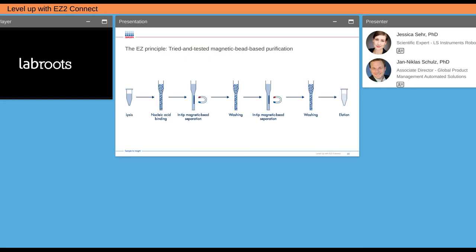So what the instrument is doing is that it works with tips inside, so it really can aspirate liquid, and with the liquid also the magnetic beads, and then a magnet can be put in close proximity to this tip to attract the beads, and the liquid can be exchanged and also transferred then to the next well, and so on and so on. And this is very unusual for an instrument in this size. Normally benchtop instruments work with static magnets and only transferring the liquid, but keeping the particles in one well. And here we can transfer, we even can add liquid in one well, which allows for a higher degree, or a maximal degree, I would even say, of automation.